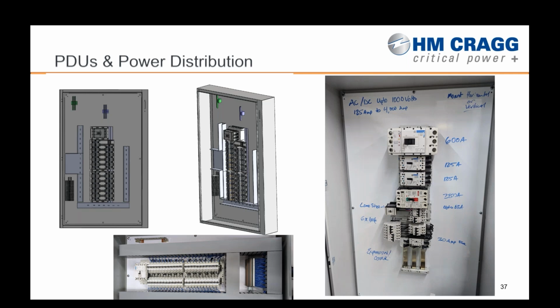One other thing that we can utilize is the ability to tack on branch and load level circuit monitoring, both on voltage and amperage, as well as being able to create controls around certain non-critical type loads and do active load management, which we found has supported a lot of UPS projects, a lot of DC projects, and the big focus is going to be battery energy storage systems, where we have non-critical loads on the system that after a certain duration of battery runtime and power is not coming back on, we can shed those non-critical loads and extend the life of that battery system.